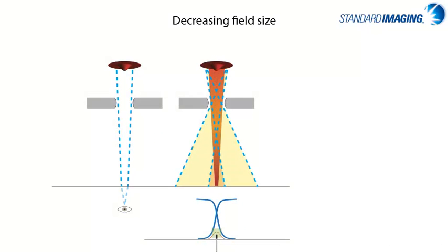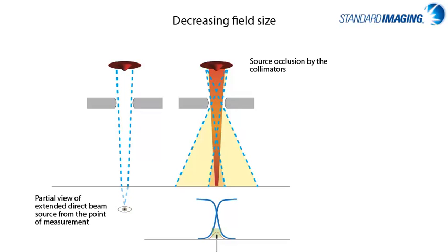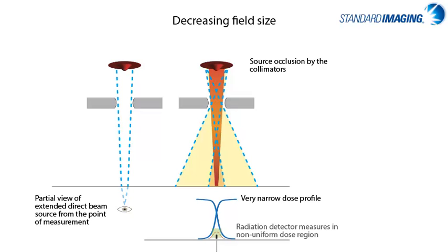However, if we decrease the field size as shown here, it becomes apparent that the source is blocked or occluded by the field defining collimators, making it difficult to not only perform measurements, but to define a field size as well, as there really isn't anywhere within the field that has a uniform dose, at least with respect to traditional active detectors.